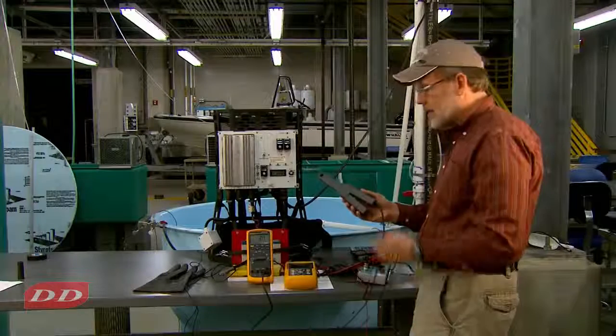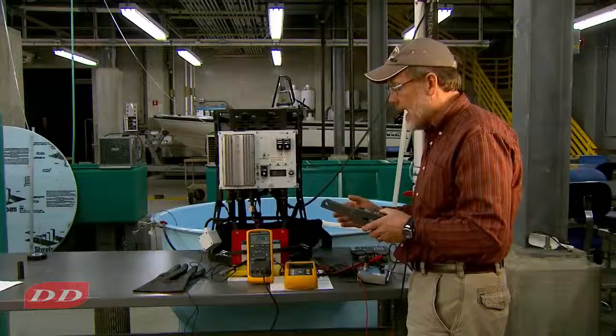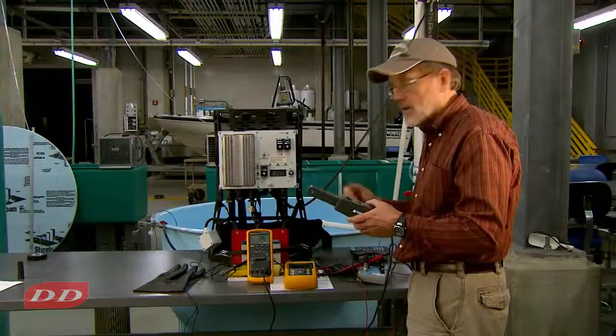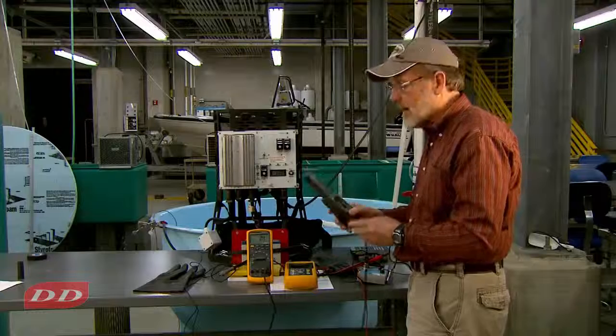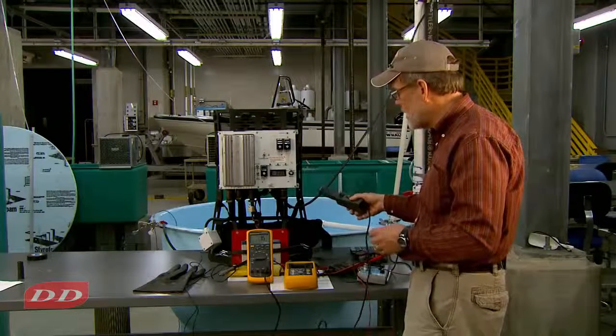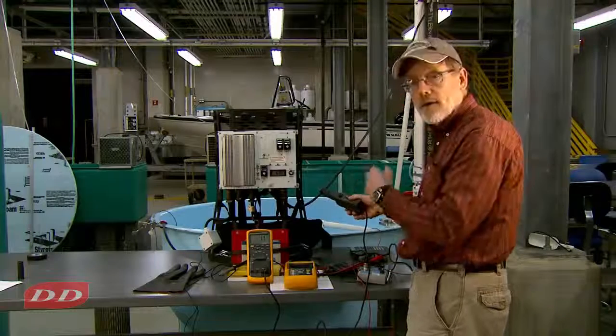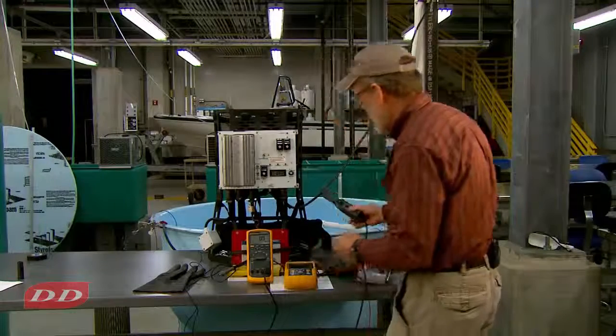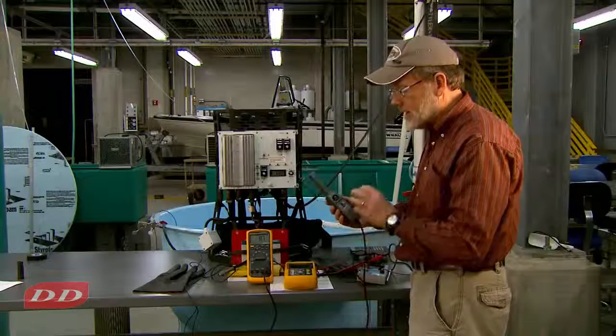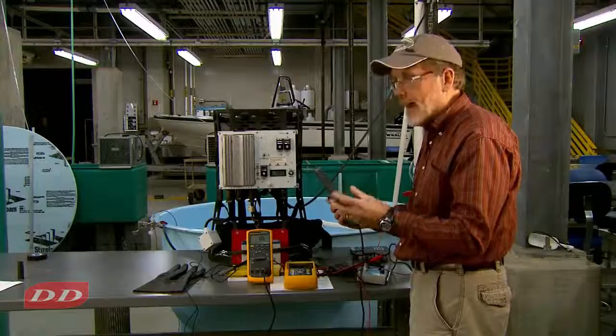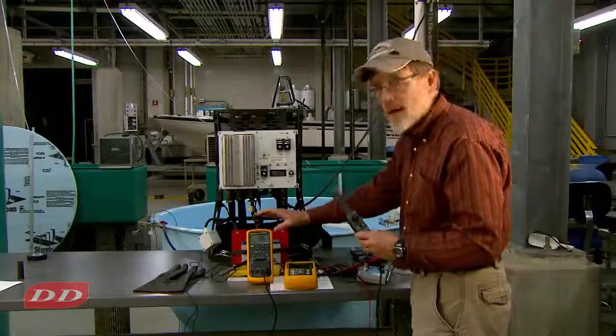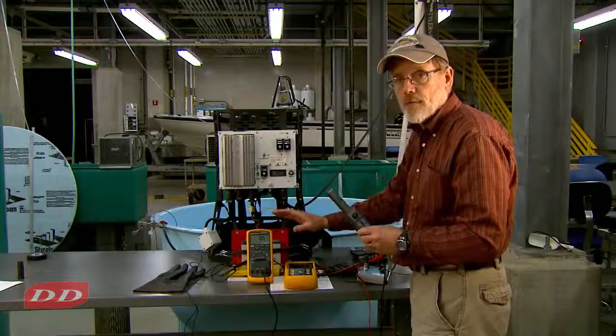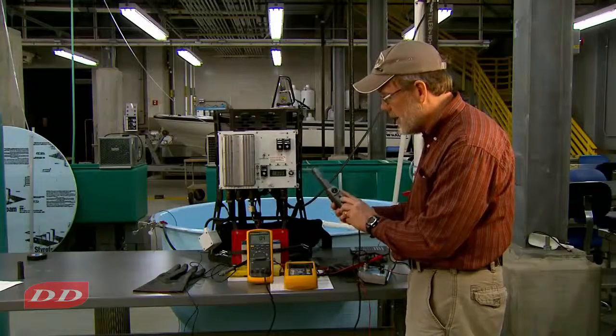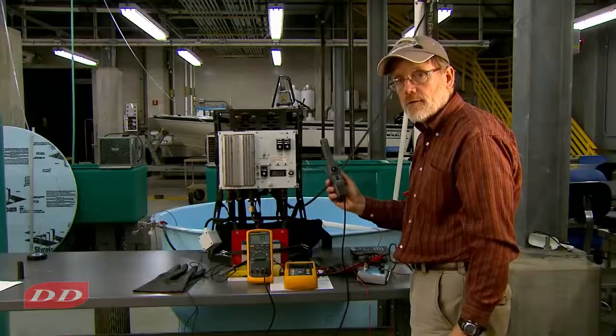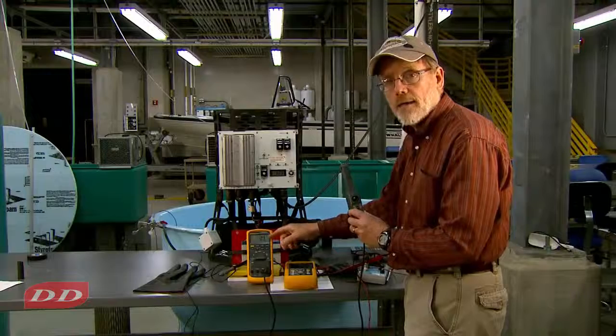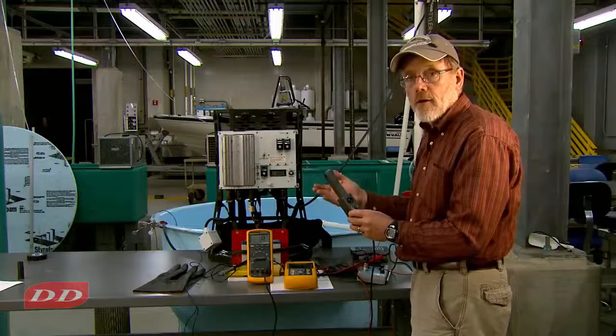So typically, at least the old way to do an amp reading was to break in line to the circuit, but now we don't have to do that. We can use what's called a clamp ammeter, where we just clamp it over either the anodic line or the cathodic line. And this clamp ammeter doesn't send directly an amp signal, it sends a voltage signal. So we have to make a conversion. We'll get voltage and we have to make a conversion to get to amperage. So here in this case, I'll turn it on and I'll set the scale to 100 millivolts per amp. So we'll get the millivolt reading here. We'll just divide that by 100. That'll give us our amperage.